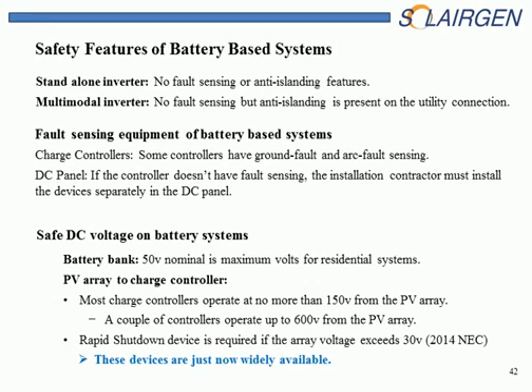Now the DC coming from the charge controller is a different story. These usually operate no more than 150 volts, but that is enough voltage to create a shock and possibly a fire. So you have hopefully metal conduit all the way to the DC system. It's required by the code, and hopefully they followed the code. But you would have to look from the PV array location to the battery-based location.